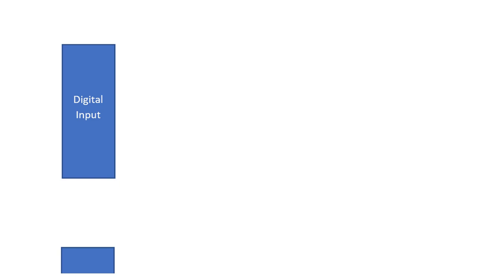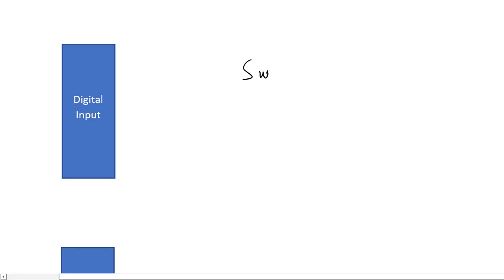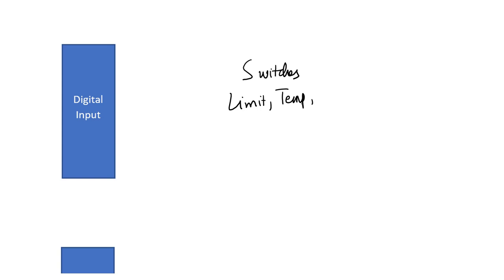Digital input cards are used for interfacing those sensors to the PLC that send digital data to the PLC. Sensors like switches, limit switch, temperature switch, pressure switch—all these switches send digital data to a PLC. The data they send is either 0 volt or 24 volt in a PLC. So these sensors are actually interfaced with digital input cards.